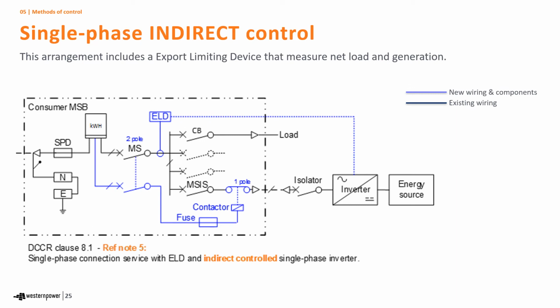Now let's look at the single phase indirect control. Some export limiting devices need to measure net load and generation, and in that situation, we need to use indirect control. Essentially, you install the single phase inverter system the same way as you've done previously. However, between the main switch inverter supply and the inverter isolator or the inverter, you install a single pole contactor, which is normally open, and a control cable with fuse protecting the coils of the contactor to the additional pole of the main switch. Western Power will terminate into the meter.